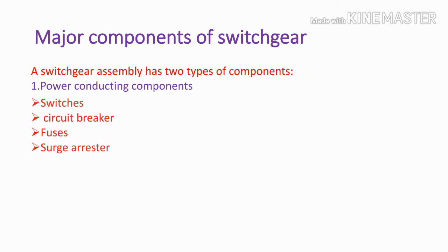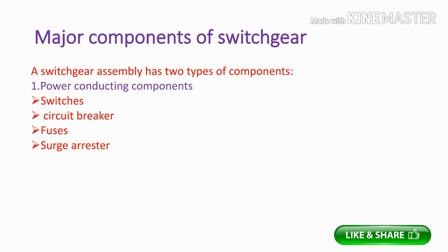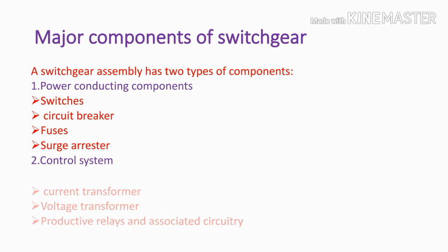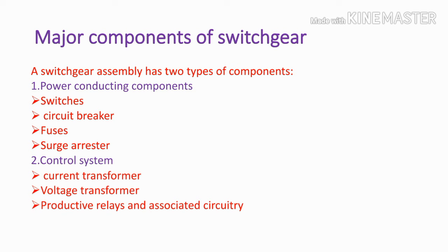There are two types of major components of switchgear. The first is the power conducting components: switches, circuit breaker, fuse, and surge arrestor. These four are power conducting components that carry high voltages. The second type is the control system components: current transformer, voltage transformer, protection relay, and associated circuitry. These control the switchgear.